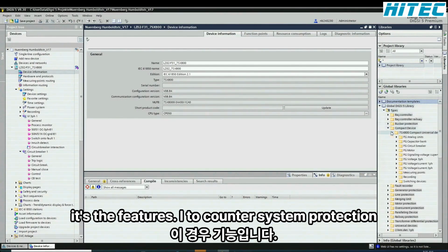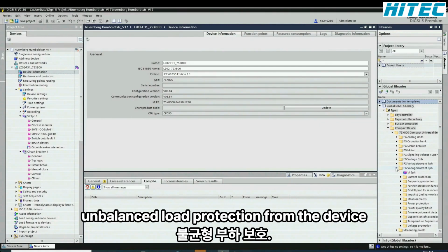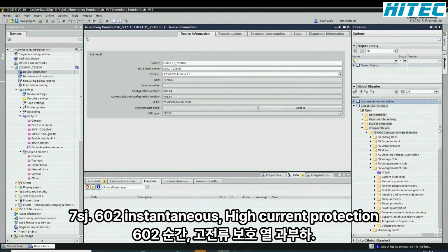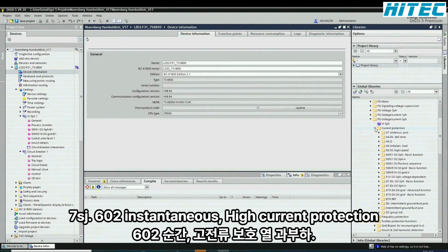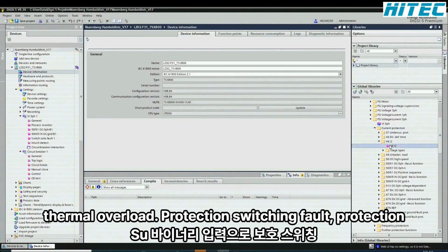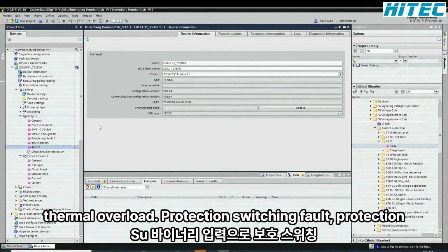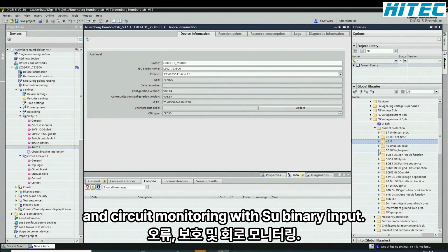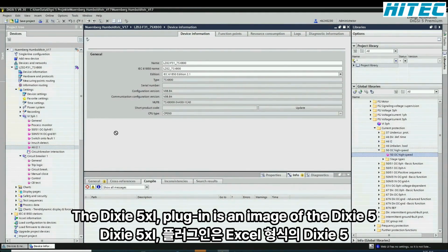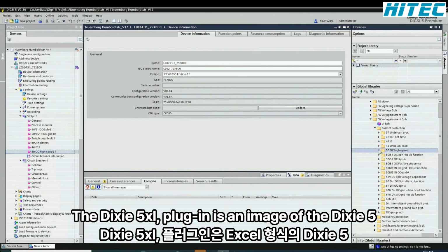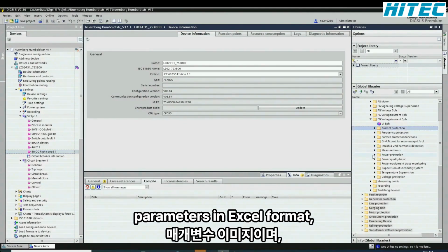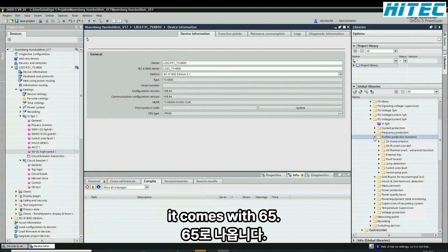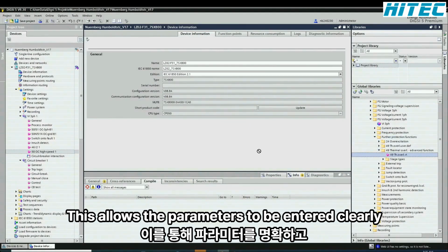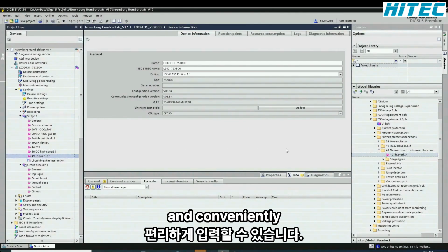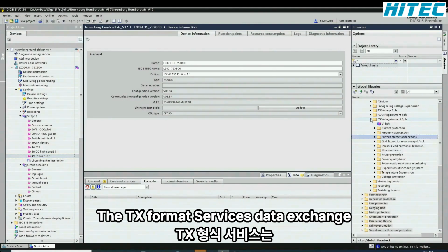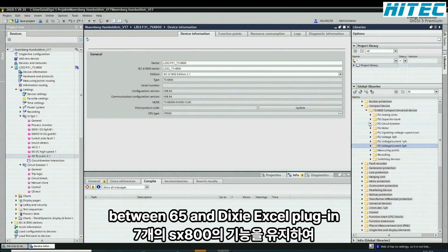I2 counter system protection as an alternative, the function unbalanced load protection from the device 7SJ602, instantaneous high current protection, thermal overload protection, switching fault protection and circuit monitoring with 2 binary inputs. The DIGSI 5 Excel plugin is an image of the DIGSI 5 parameters in Excel format. It comes with DIGSI 5. This allows the parameters to be entered clearly and conveniently. The TX format serves as data exchange between DIGSI 5 and the DIGSI Excel plugin.